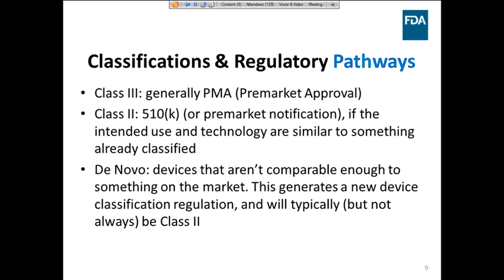Another question that might arise is when is clinical data needed, especially when human studies need to be initiated and are significant advanced investments by sponsors and investigators, which FDA realizes. Typically for PMAs, clinical data is needed. For de novo submissions, typically clinical data may be needed, but may not always be needed. And for 510K submissions, clinical data is typically not needed, although there are cases where clinical data was submitted.